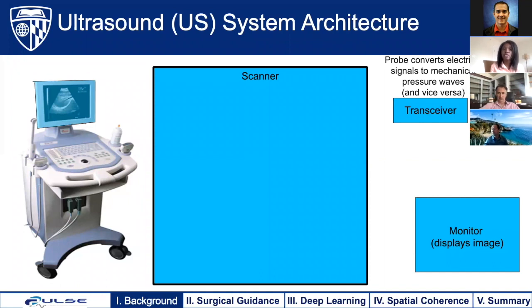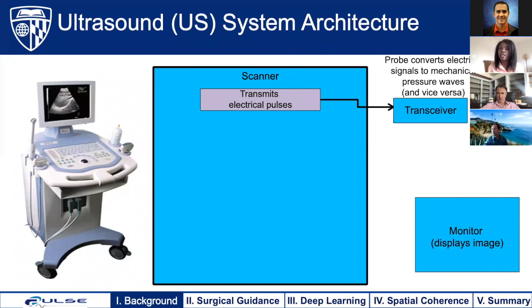The way that these three components interact is that the scanner transmits electrical pulses to the ultrasound probe, which contains an array of piezoelectric elements that convert the electrical signals into mechanical pressure waves that are propagated into the body. These mechanical pressure waves then reflect off of different structures in the body and return an echo to the ultrasound probe, which uses those same piezoelectric elements to now convert the mechanical pressure wave into electrical signals.